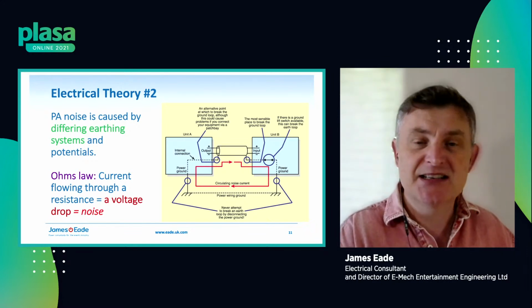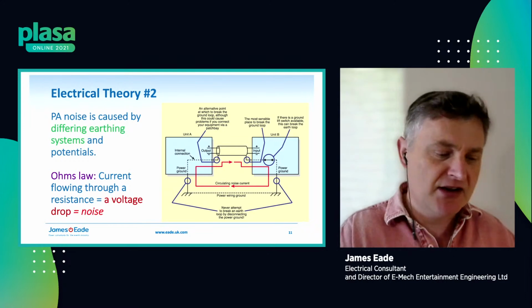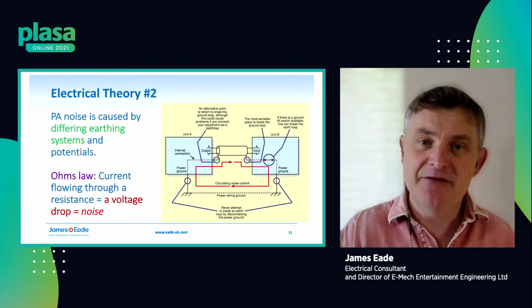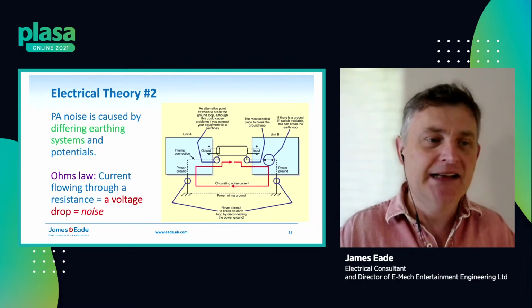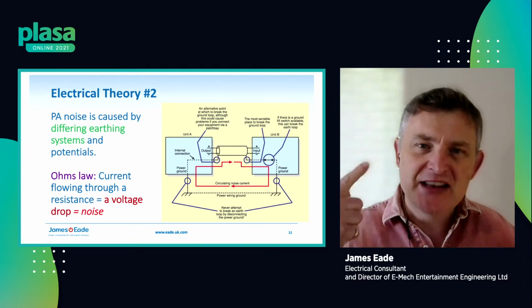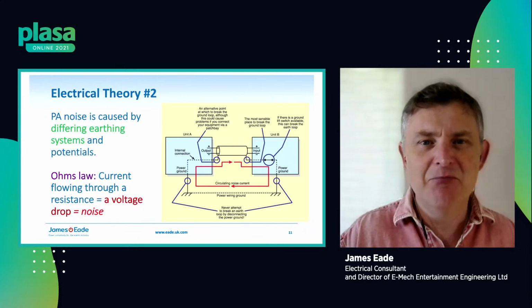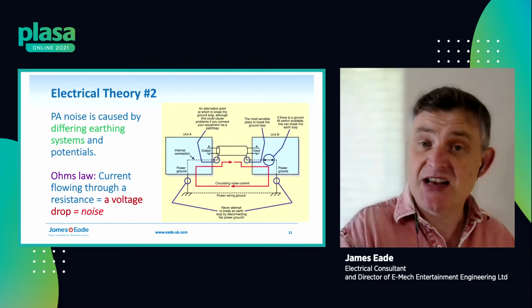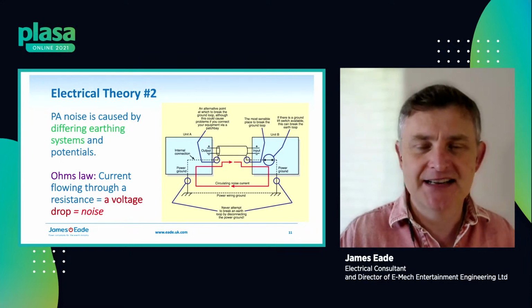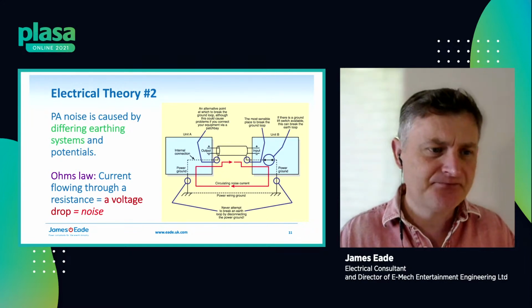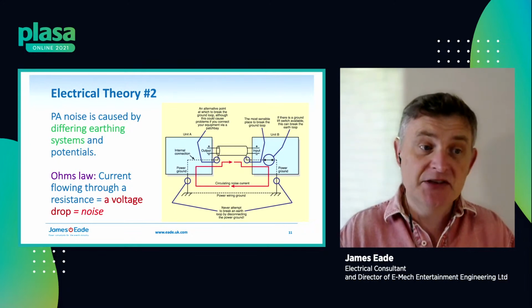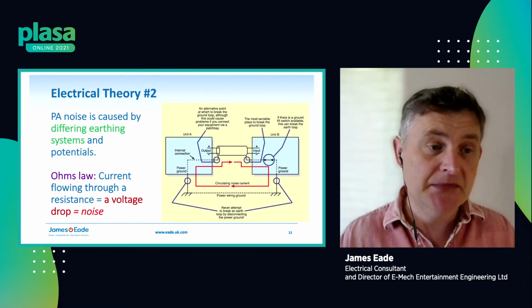And when someone says that and you're rigging some lights, they say, oh no, you can't have them together, because if you get a fault, you might have a 400 volt shock or similar. And when you think about it, you think, oh yeah, that doesn't sound implausible. But when you look at the safety requirements, it's a non-starter. So very much good practice to have separation between them.